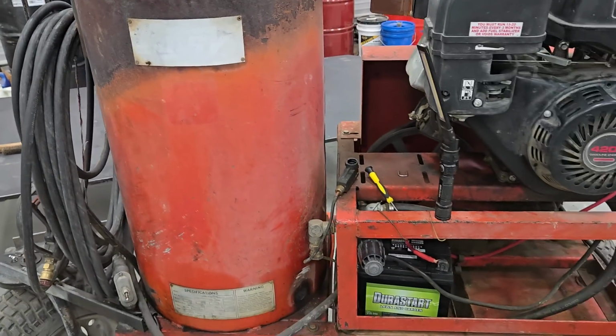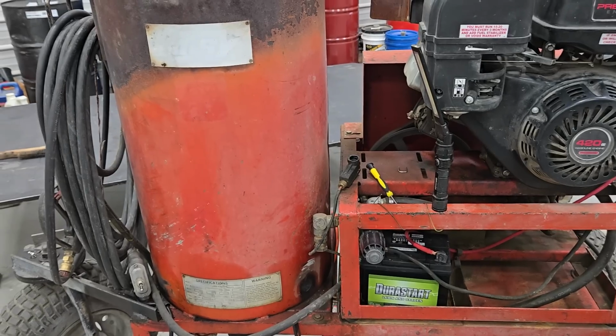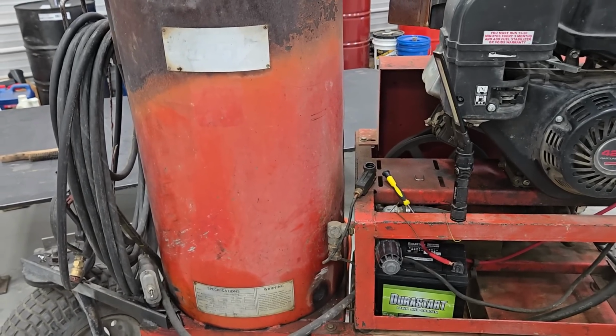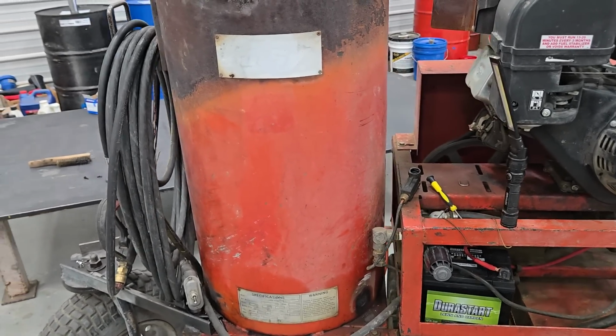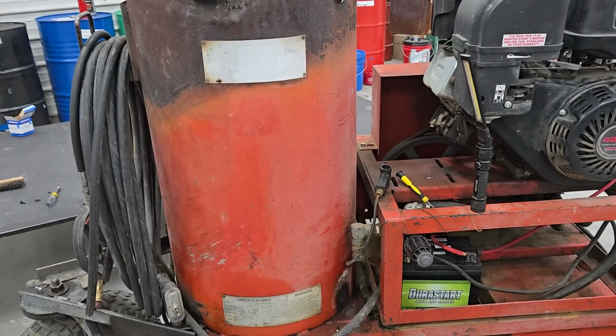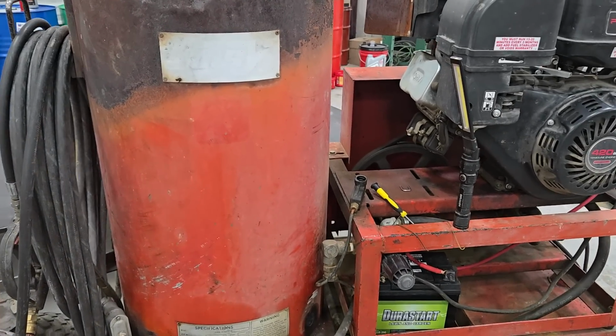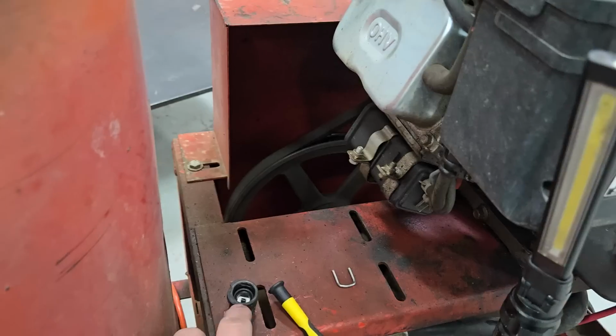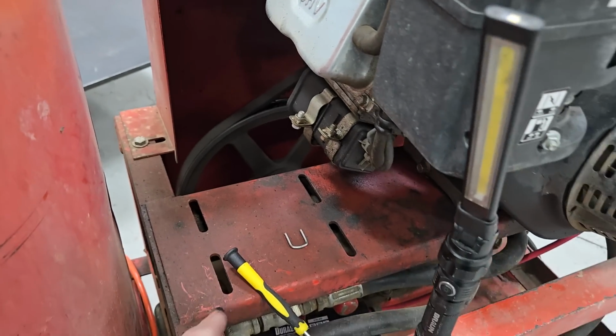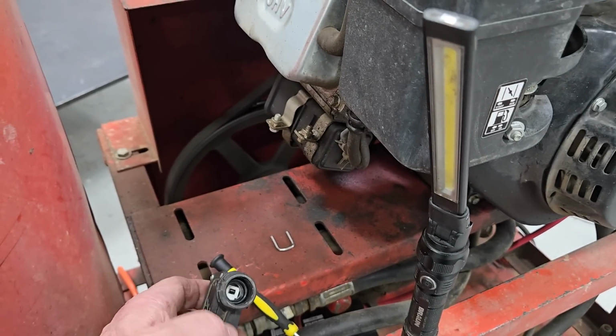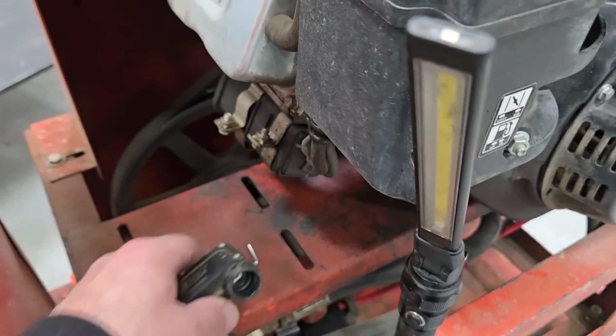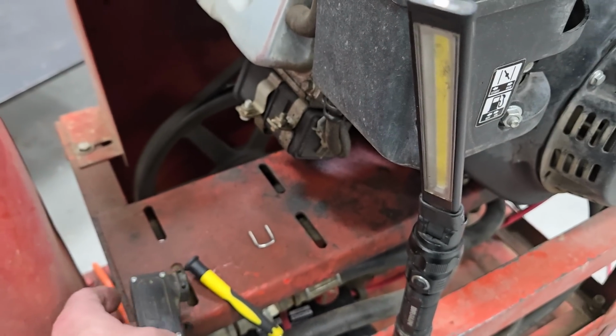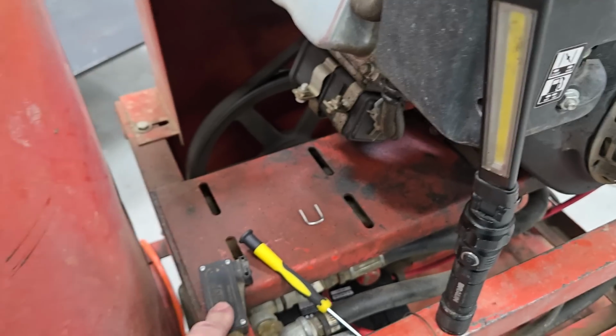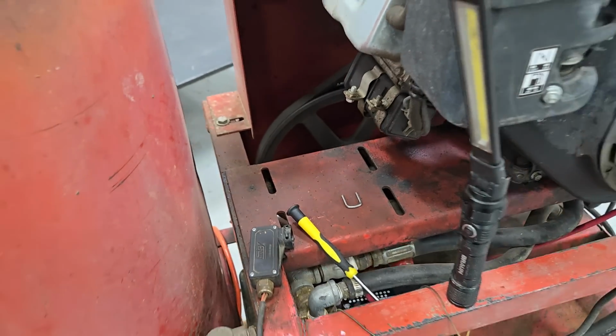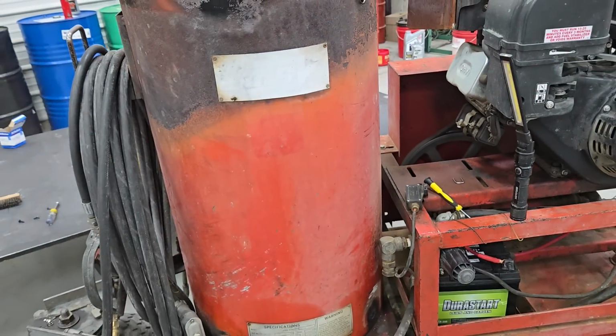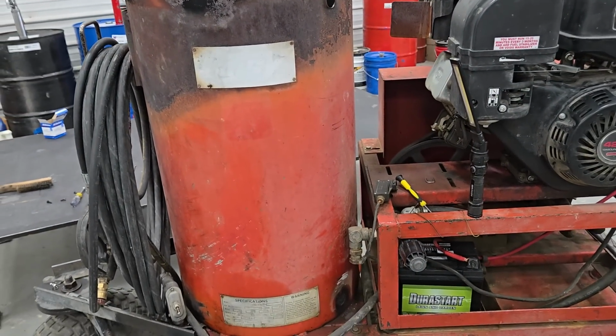So a lot of guys said to clean my electric eye - this model does not have an electric eye. The only thing it has on it to keep you from blowing your head off is this pressure switch, and it goes in over here on the valve. Put it in, you put this hog ring on it. It's just a micro switch. If this goes bad, you have to be paying attention - if you let go of the trigger and you don't hear that boiler shut off, you're going to have problems.